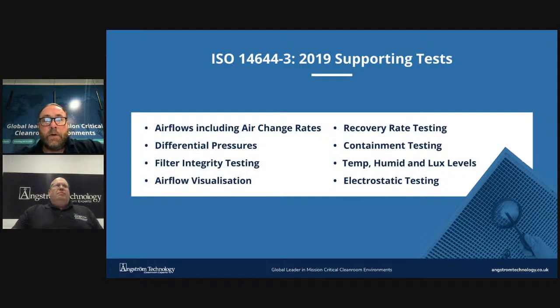Containment testing also requires the use of a smoke generator, and dependent on whether the room is positively or negatively pressured, will determine where the smoke is released. The leaks are then detected using either a particle counter or photometer. Temperature, humidity, lux, and electrostatic testing will all require various specific instruments to complete the tests.